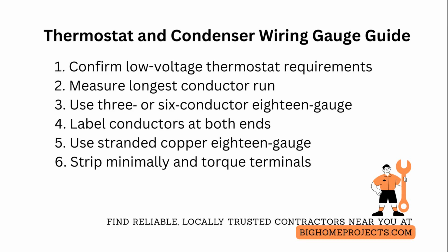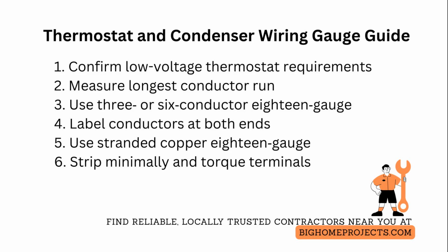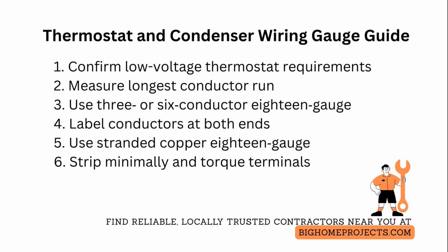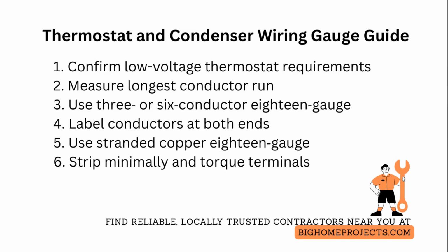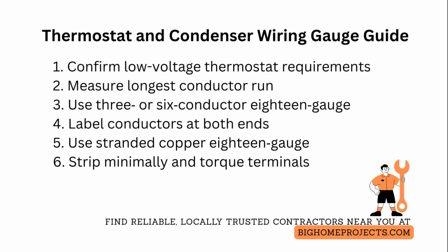Measure the longest conductor run and keep it under the manufacturer's specified maximum for voltage drop. Use 3-conductor 18-gauge for basic condenser control and 6-conductor 18-gauge for multifunction thermostats that handle heat, cool, fan, and common power. Label each conductor at both ends with durable tags or heat shrink labels so future techs can trace circuits quickly. Pull stranded copper 18-gauge, not solid, where the cable will see movement or be routed through flex conduits to avoid breakage.